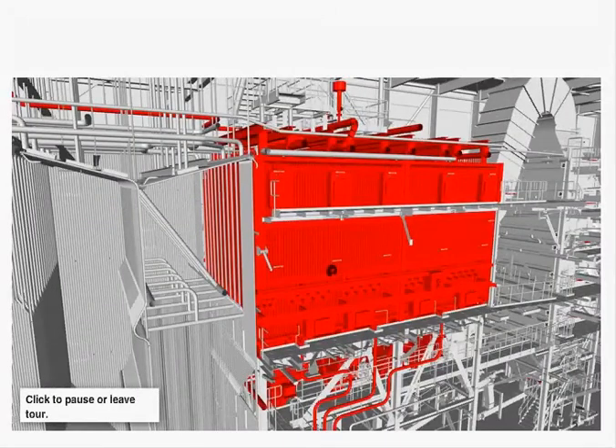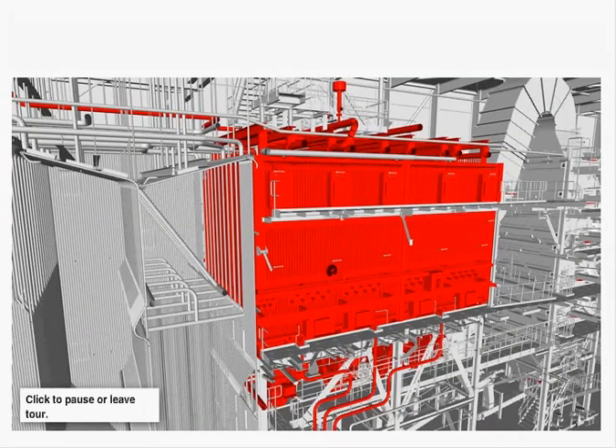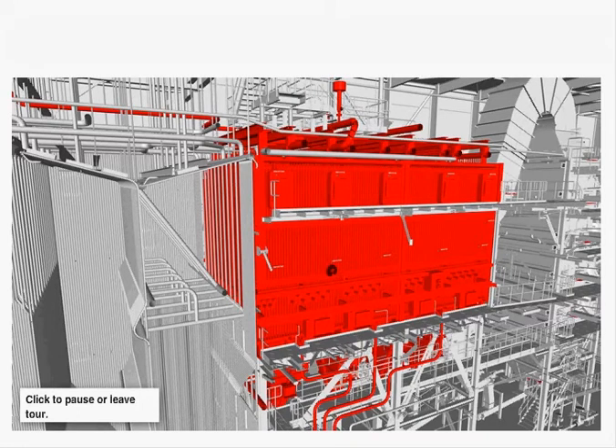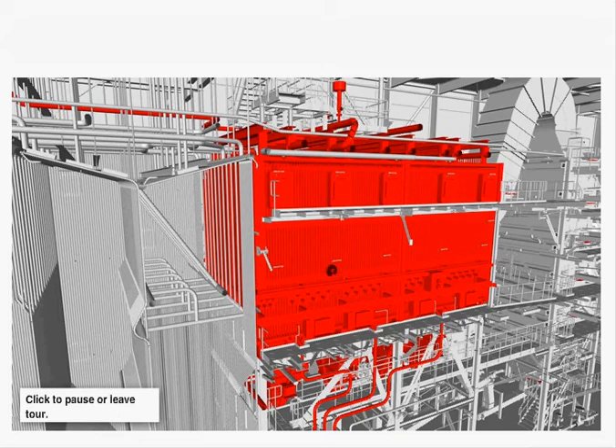The convection part consists of our superheater section followed by an economizer. Both of the sections can be either horizontal or vertical, depending upon the layout of the plant. Here at the Meath County Waste to Energy Plant, the convection part is horizontal and the economizer vertical. The superheater section is made up of a number of tube bundles, in which steam is superheated before it goes to the steam turbine. The steam turbine produces electricity for the community.